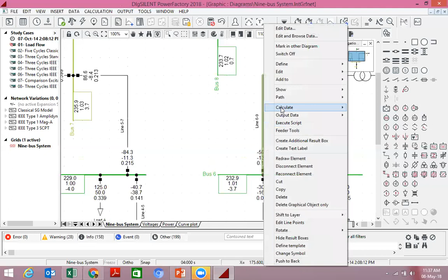So these methods have different ways of calculation. The default one is, I'm selecting this VDE, that is German standard, and the year in which these methods were published - these are the three methods, 1996, 2001, and 1990. What is the fault type we have? 3-phase, 2-phase short circuit, single phase to ground, 2-phase to ground, 1-phase to neutral, and all those things.